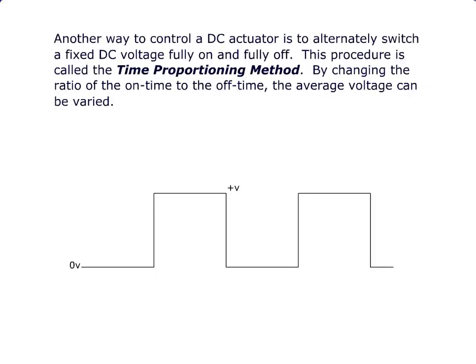Another way to control a DC actuator is to alternately switch a fixed DC voltage fully on and fully off. This procedure is called the Time Proportioning Method. By changing the ratio of the on time to the off time, the average voltage can be varied.